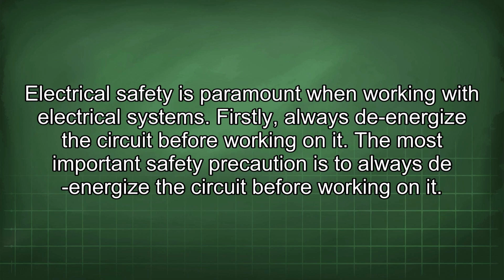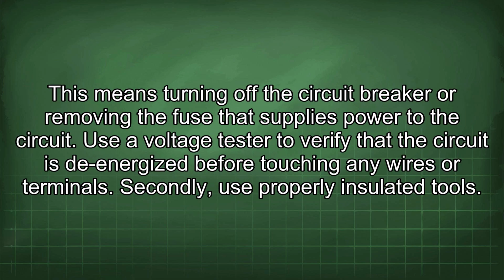Electrical safety is paramount when working with electrical systems. Firstly, always de-energize the circuit before working on it. The most important safety precaution is to always de-energize the circuit before working on it. This means turning off the circuit breaker or removing the fuse that supplies power to the circuit. Use a voltage tester to verify that the circuit is de-energized before touching any wires or terminals.